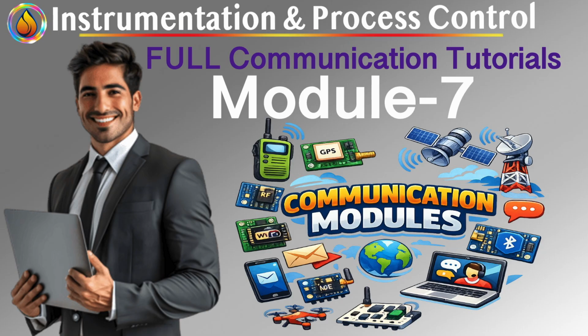Why the classic OSI model wasn't enough for process control. OSI was designed to solve a communication problem. How do heterogeneous systems exchange data reliably? It was not designed to solve a control problem. How do heterogeneous devices execute identical behavior? OSI can guarantee bits arrive, frames are intact, messages are routed. OSI cannot guarantee a valve from vendor A behaves like a valve from vendor B, that a PID block executes with the same semantics everywhere, or that control logic is portable across manufacturers. For office networks, that's fine. For process plants, it's unacceptable.